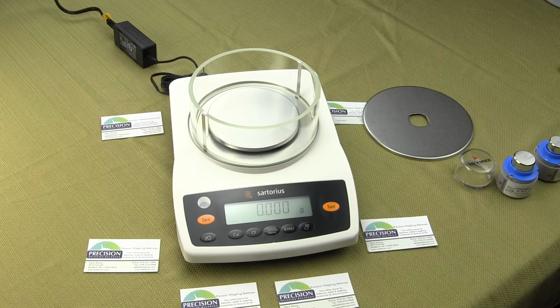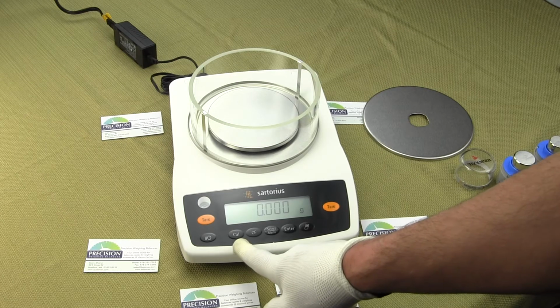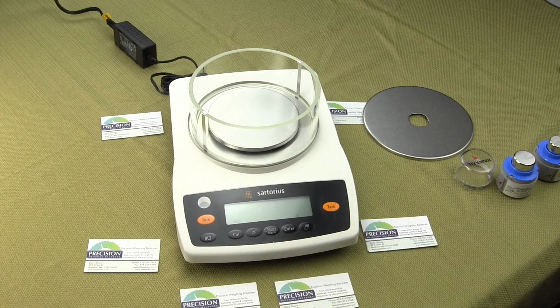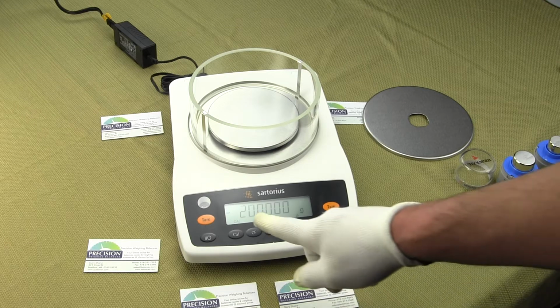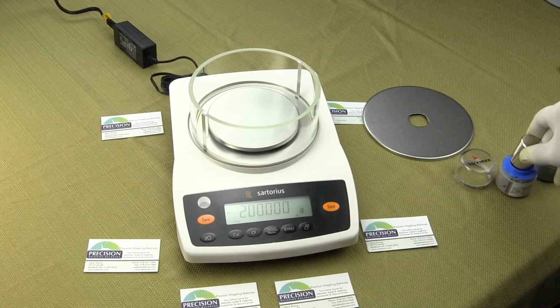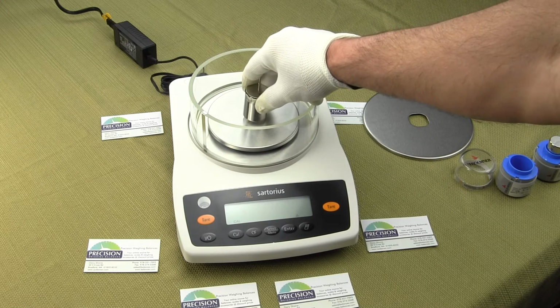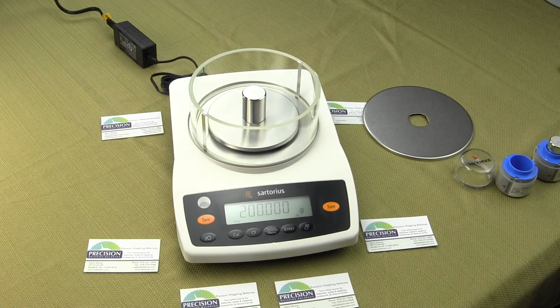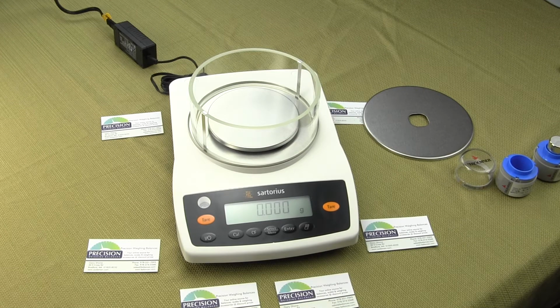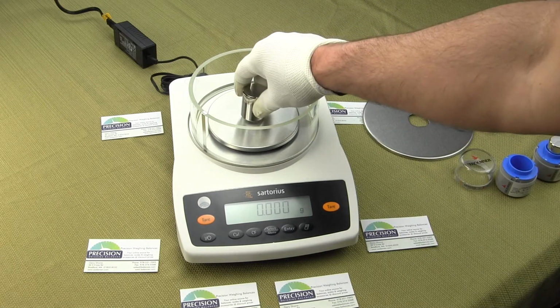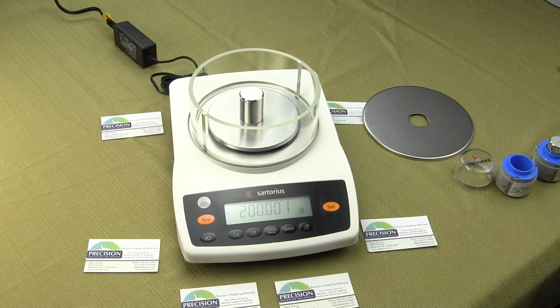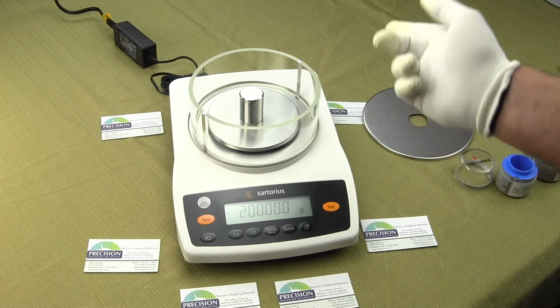So to perform calibration is extremely simple. All one needs to do is press the cal button. The display shows external, and the balance is telling us we need a 200 gram weight. All one simply needs to do, place the mass in the center of the platform, and the balance will store that value. It says cal in, calibration has been completed, and you can see it's 200. We can take the weight off, put the weight back on, and that's as simple as it is.